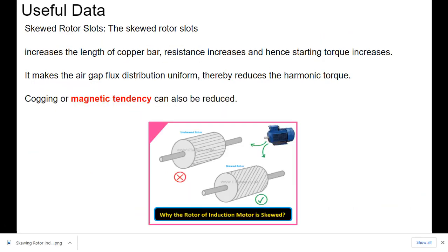Let us have a brief discussion on these machines. Skewing in induction machines, the rotor or the stator slot of the induction motor is skewed through some angle so that the bars lie under alternate harmonic poles of the same polarity. Or you can say the bars must be skewed through two pitches.